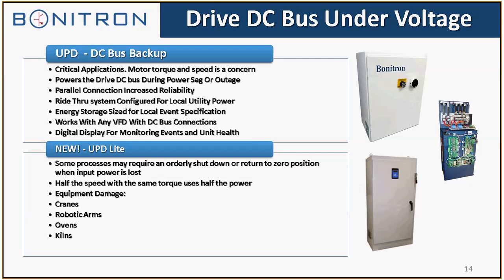Where this becomes important is that when you specify the ride-through, you may have only specified it for sags, but you may find out you're having very short-term outages. We can retrofit sag ride-through with ultracapacitor or electrolytic capacitor energy storage.